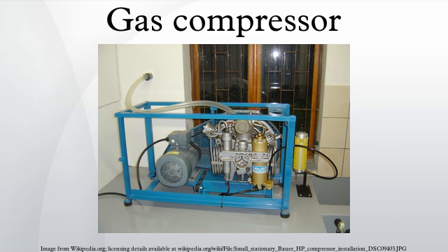A further disadvantage is that burnt-out windings can contaminate whole systems, thereby requiring the system to be entirely pumped down and the gas replaced. Typically, hermetic compressors are used in low-cost factory-assembled consumer goods where the cost of repair is high compared to the value of the device, and it would be more economical to just purchase a new device.